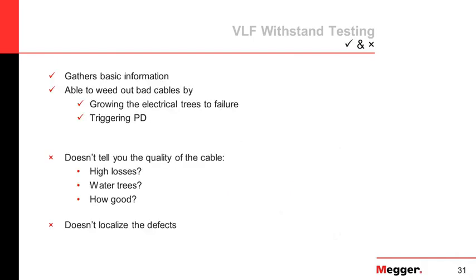Overall, the withstand test gathers basic information about your cable. You can weed out bad cables by growing electrical trees to failure in a controlled environment. Unfortunately, the withstand test doesn't tell you how healthy your cable is — like whether you have small water trees or what quality the insulation is — and it doesn't localize defects. But this is the essential purpose of withstand testing.